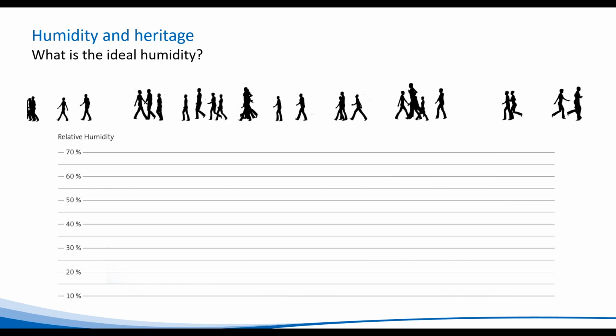So let's now look at, well, we know we've got a humidity demand, but what is the ideal humidity? Well, optimum humidity for human health is 40 to 60% RH. At this level, people feel comfortable and skin doesn't dry so readily, and contact lens wearers express fewer complaints of sore eyes, and static is largely eliminated. And importantly, airborne respiratory cross-infections are minimised, and this is due to our respiratory immune systems being most robust and effective in this range, and airborne viruses having lower infectious lifetimes in this range. So for people, 40 to 60 is ideal, and we can cope very readily with that swing of plus or minus 10.